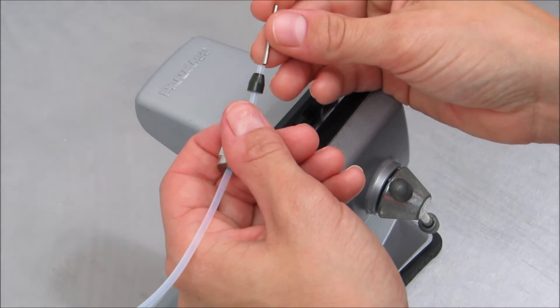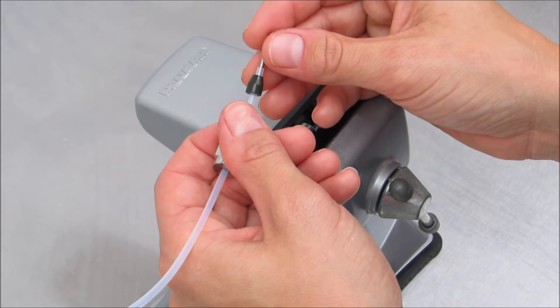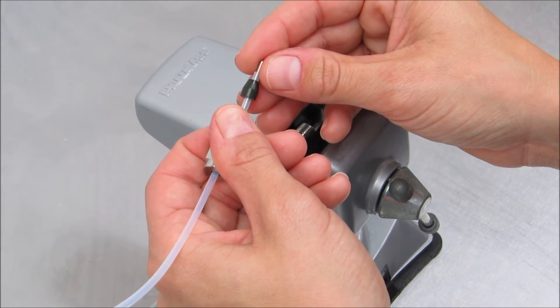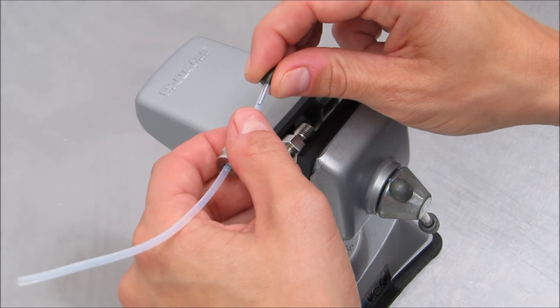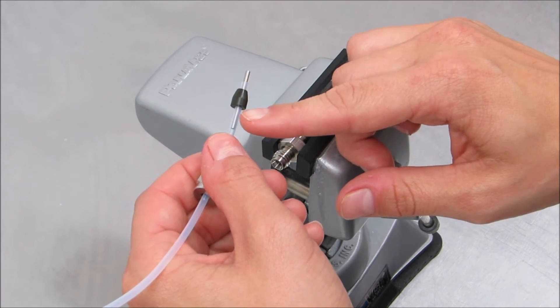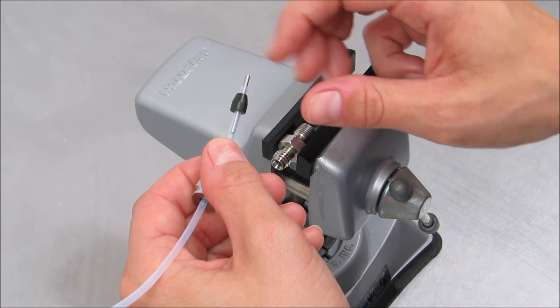Then, place the stainless steel insert into the PTFE tubing, making sure the insert remains at least a sixteenth of an inch from the end of the PTFE tubing. You should also be able to see the insert past the flat side of the ferrule extending no less than an eighth of an inch.